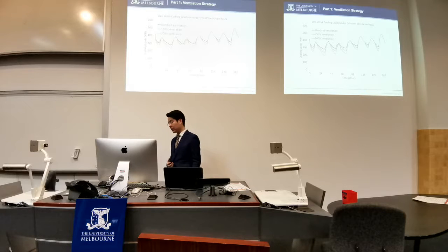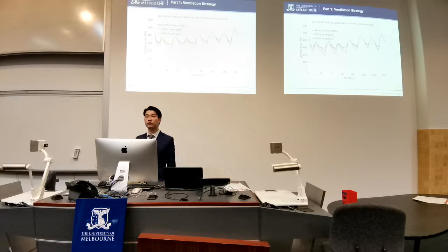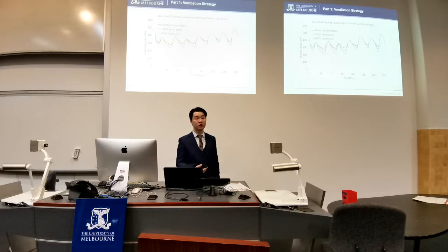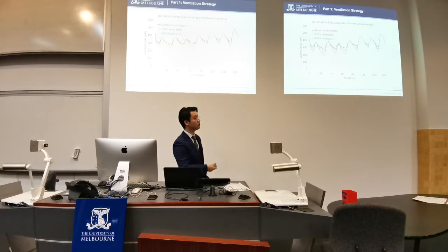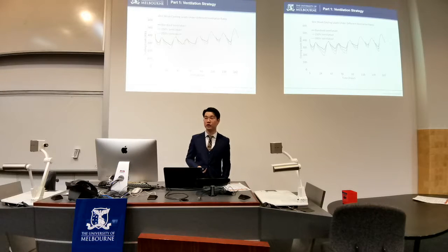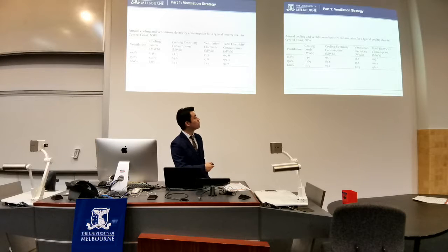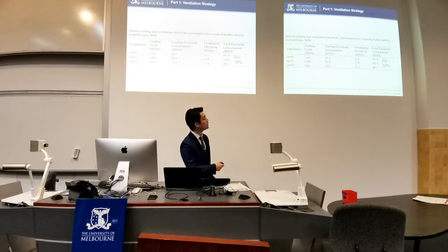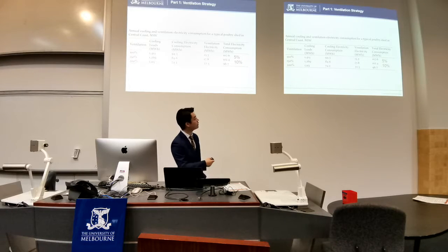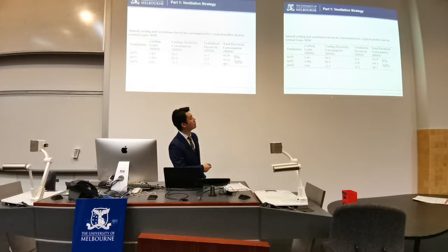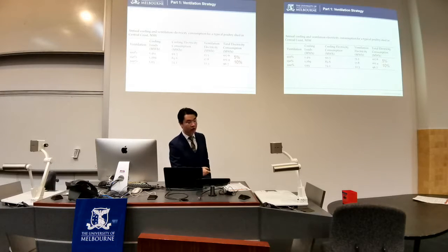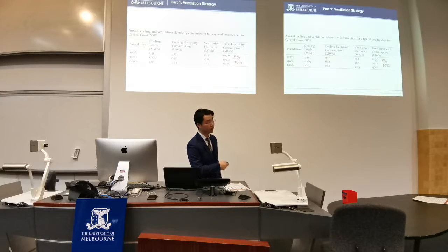One thing we need to consider is that when we do such ventilation, we are expected to consume more electricity for the fans. That's why, when evaluating it, we also need to consider the electricity consumed by the fans. But even if we sum it up, we could still expect a 5% reduction in cooling costs if we increase the ventilation rate by 50%, and about a 10% decrease in the total cooling and ventilation costs if we increase it by 100%.